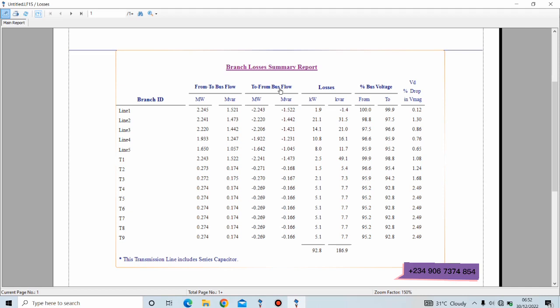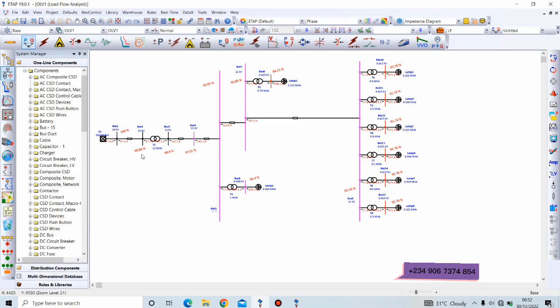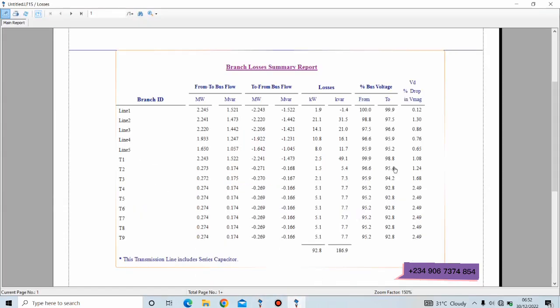This is from both—when what is coming in is this, what is going out is this. Now these are the losses. This is my primary concern—the losses. But before I go into that, let me explain this side. From the bus which is connected to—let's take line 1 as an example. Line 1 is from bus 1 to bus 2. From bus 1, bus 1 is at 100% operating voltage—we check 100%—while bus 2 is at 99.88%. But here it approximated it, so we have 100% to 99.9%. The voltage drop now is this minus this, which is why we are having 0.12 here. The voltage drop is this minus this—removing this from this we have this. That is how we have our voltage drop.